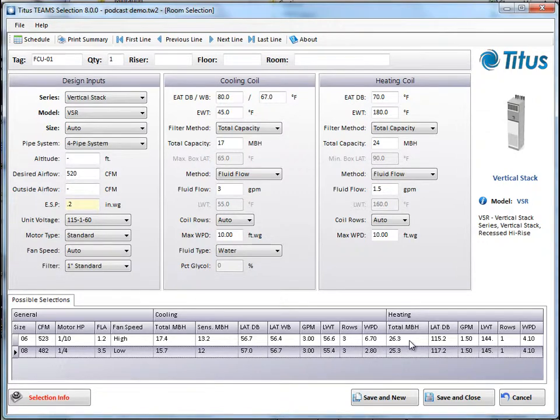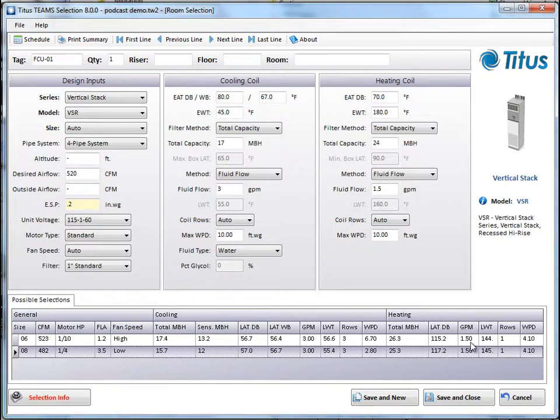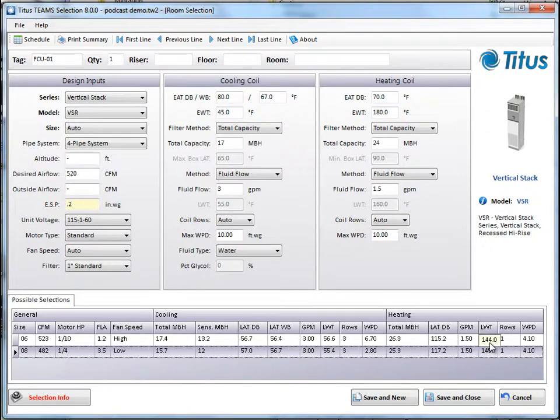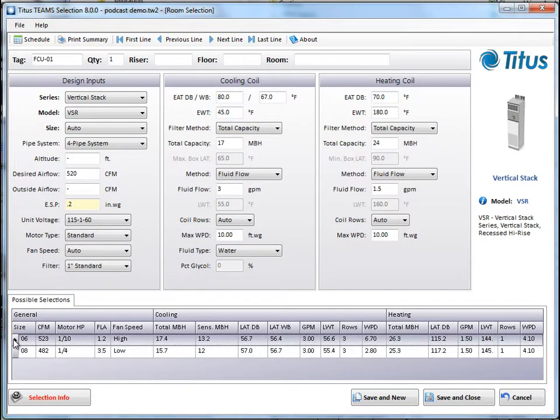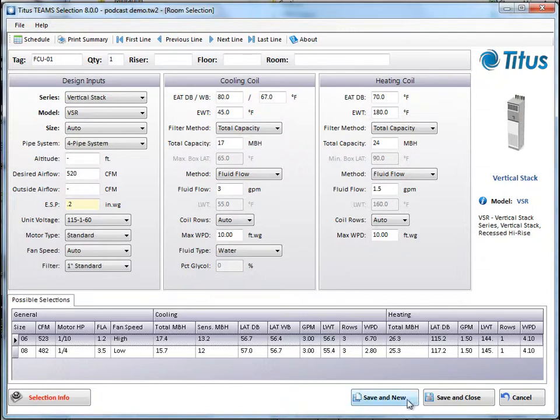And then you can see the same information for heating, 26 MBH, leaving air temperature, dry bulb of 115, 1.5 GPM, leaving water temperature of 144, one row, and a water pressure drop of 4.1 feet. So let's say we want to select the size 6.